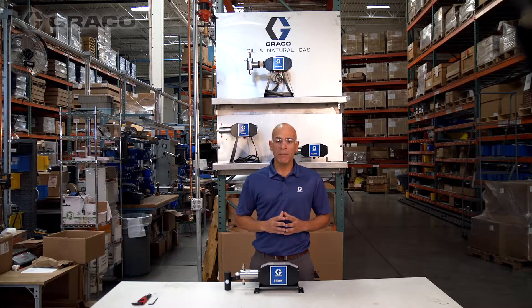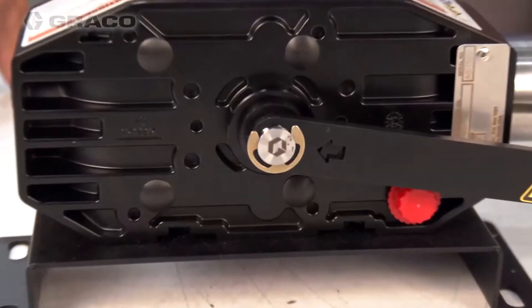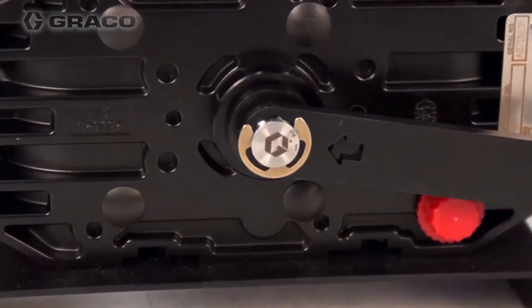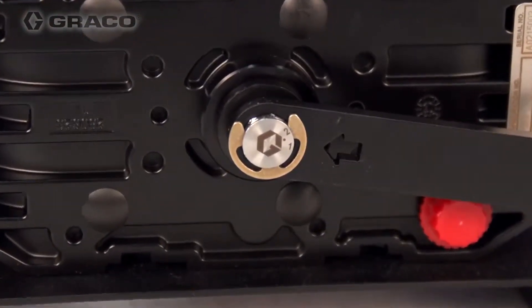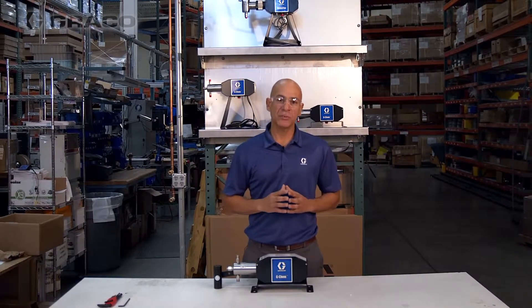The GChem beam pump comes with three different plunger sizes and three different seal materials. It is also designed with a unique stroke adjust fine-tuning feature that helps with smaller stroke increments. This is achieved with a unique octagon-shaped shaft design that gives you additional stroke settings for each stroke adjustment position.